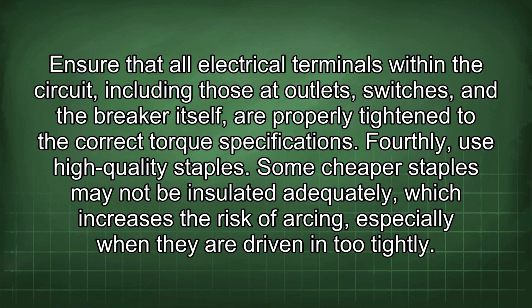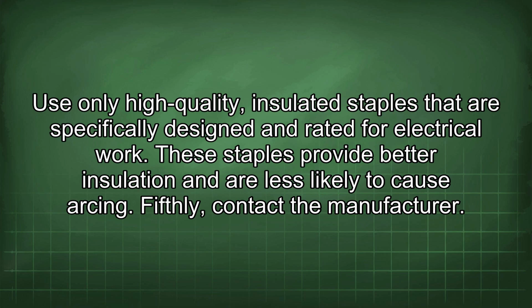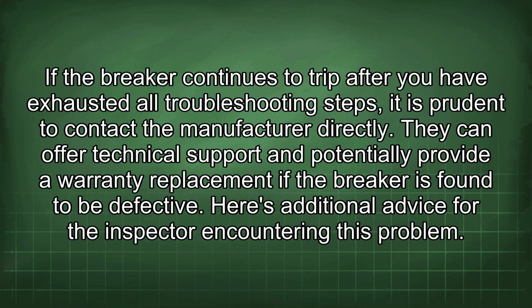Fourthly, use high-quality staples. Some cheaper staples may not be insulated adequately, which increases the risk of arcing, especially when they are driven in too tightly. Use only high-quality, insulated staples that are specifically designed and rated for electrical work. These staples provide better insulation and are less likely to cause arcing. Fifthly, contact the manufacturer. If the breaker continues to trip after you have exhausted all troubleshooting steps, it is prudent to contact the manufacturer directly. They can offer technical support and potentially provide a warranty replacement if the breaker is found to be defective.